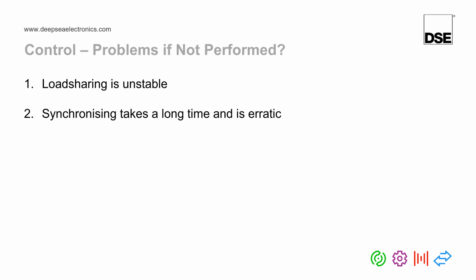Yes, my generator, just a second. How come I can't get the exact result when adjusting the AVR and governor? This is because the slider itself is stepped. You won't have an issue during load sharing because the adjustment is much finer.